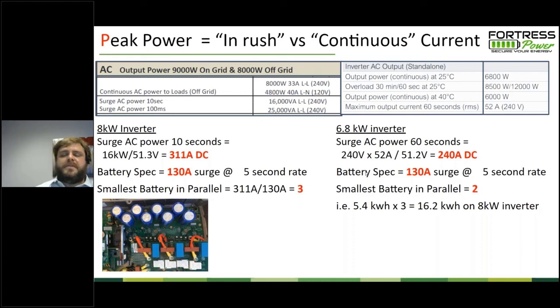We also have these 1 minute ratings for the inverters that are even higher than that, and these 100 millisecond ratings that are even higher than that. Traditionally, inrush current refers to millisecond loads, or maybe up to a 5-second load. So an inrush current would be very short duration.